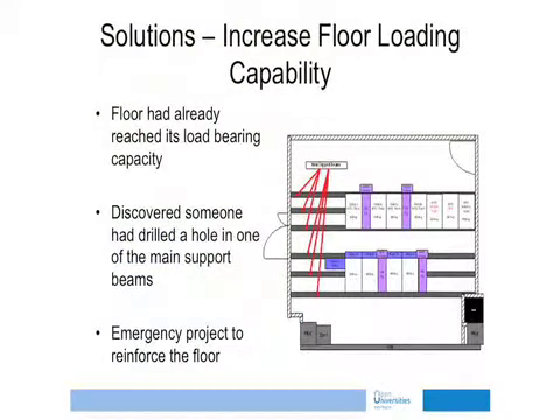The first thing we looked at was the load bearing on the roof, because air conditioning or chiller units go onto the roof, and we checked that out, that was fine. What we didn't check out was the floor. After we reviewed this, we had to actually put in steel beams to reinforce the floor, so that's something to remember for everybody else doing data centres.